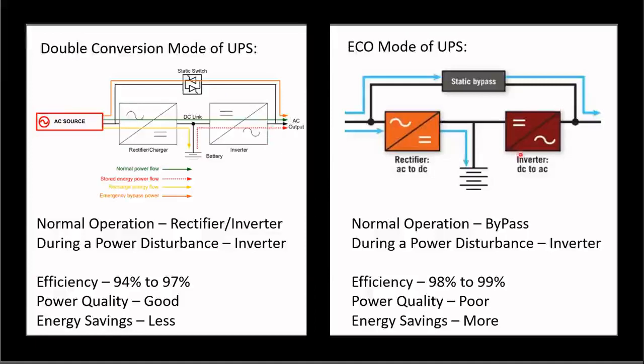Now the eco mode. In eco mode, power will not flow through that path. Power will flow through the static bypass, and some of the power will also flow through the rectifier to charge the batteries. If something goes wrong with the utility power, then the batteries will supply the load. So this is the difference here.